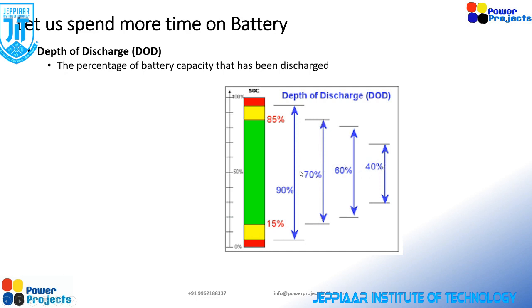This you can set in the battery management system available with the battery, which determines the maximum SOC the battery can have. The battery management system measures SOC continuously, and based on that sends information to the charging unit about what rate to charge or when to stop. So if I set maximum SOC at 85%, as soon as the battery reaches 85% SOC, the battery management system tells the charging station to stop charging beyond that point.